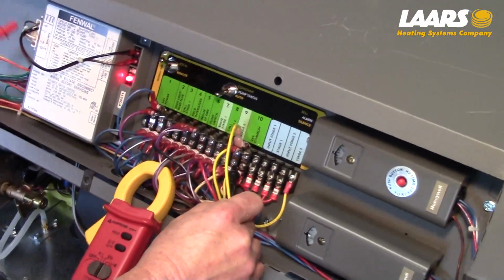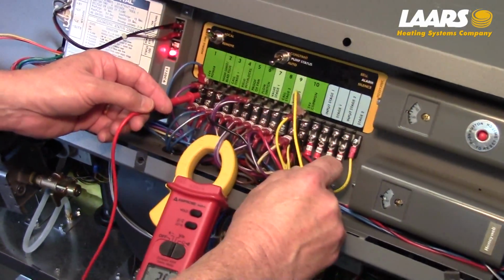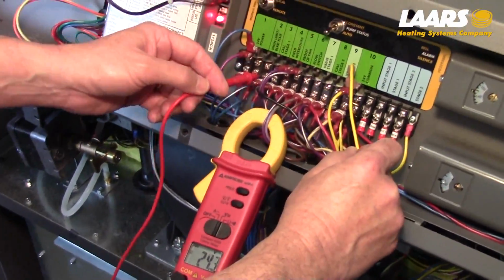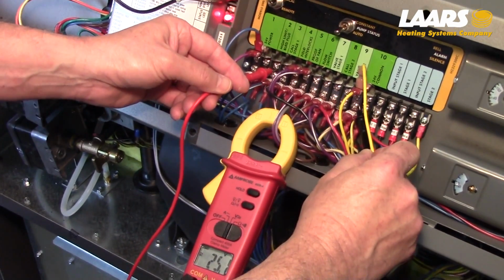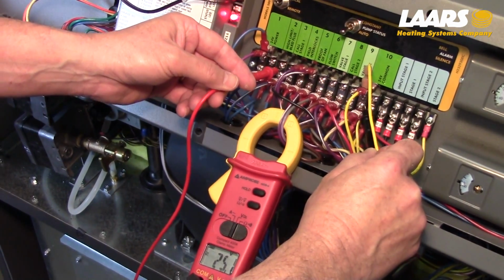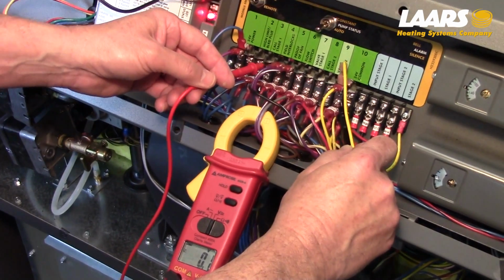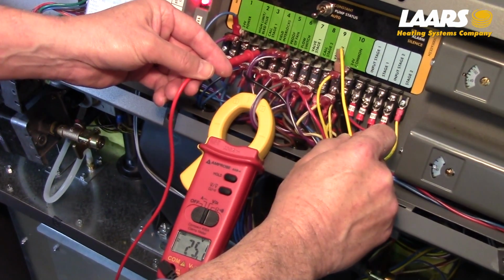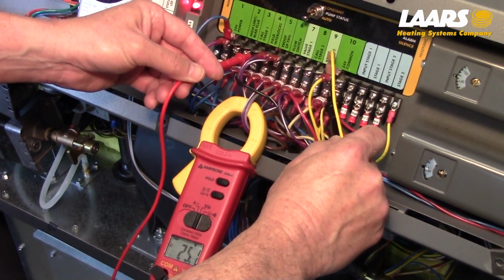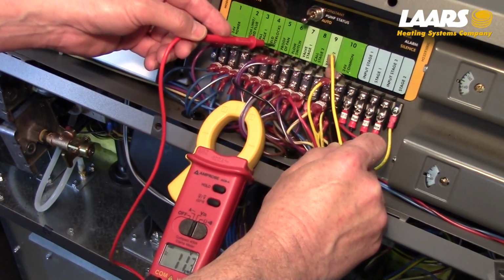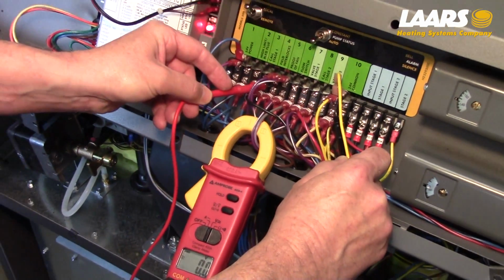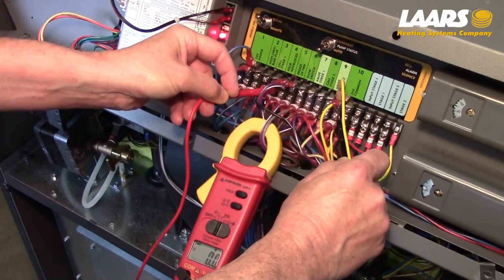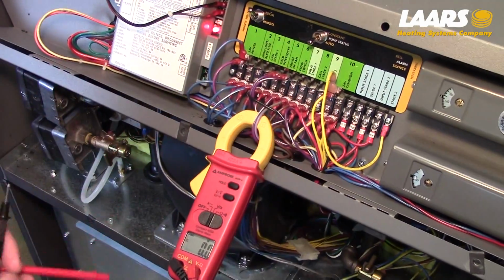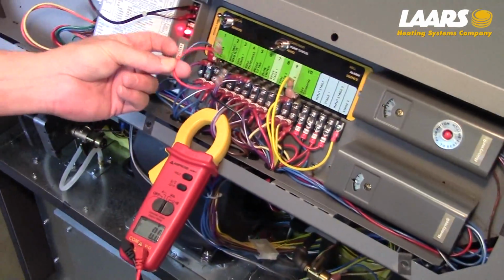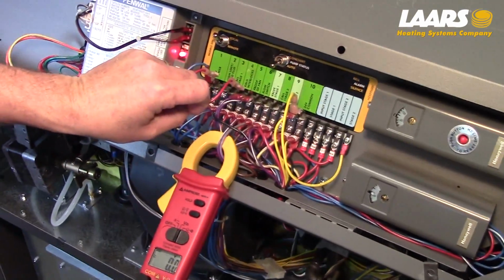So now that you can see I've reset the gas pressure switch, I'll start at terminal 1, I have it, and terminal 2, I now have 25 volts. I'm then going to go to terminal 3. Here's my terminal 3, I have 25 volts there. Terminal 4, which it says field interlock, okay, I'm going to go there and I do not have voltage there. This, as it leaves the factory, will have a jumper wire on terminal 3 and 4.